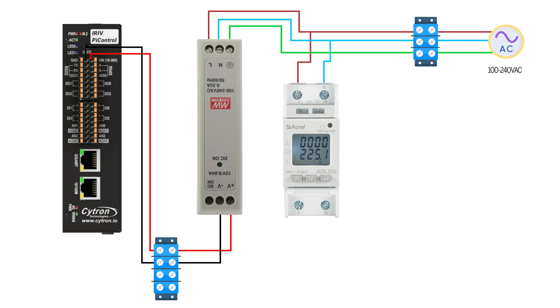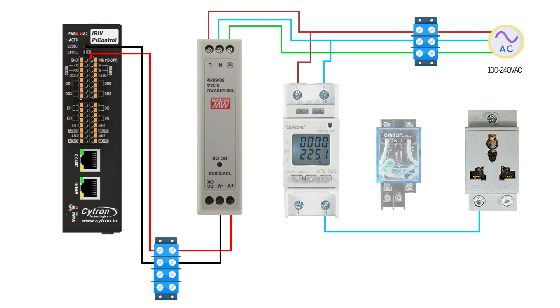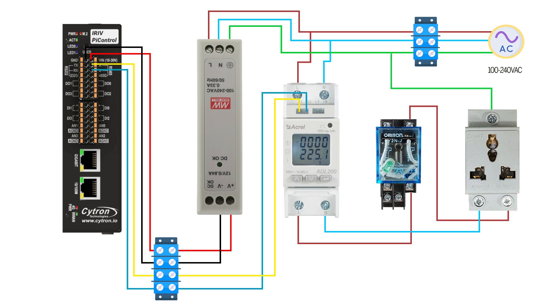Connect the N terminal of the power meter to the N terminal of the load. For the L terminal, it should be connected to one side of the relay while the other side of the relay connects to the L terminal of the load. Connect terminals 21 and 22 to the RS485 pins on the IRIV. Connect one end of the relay to the power supply.